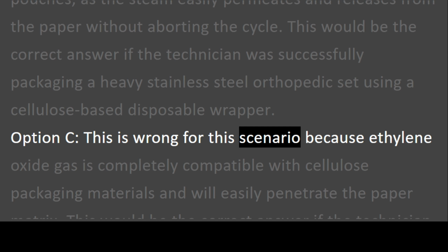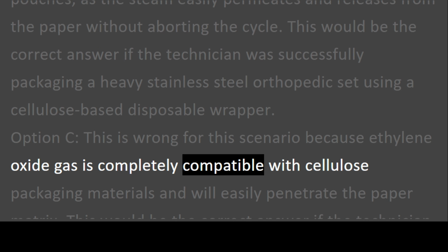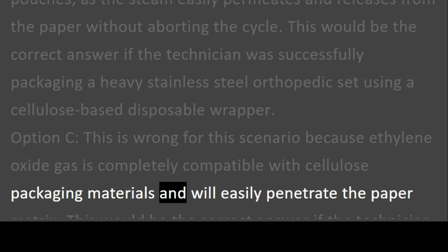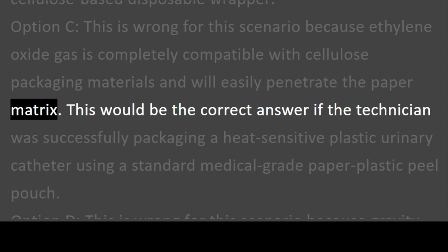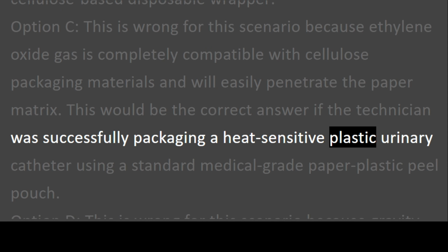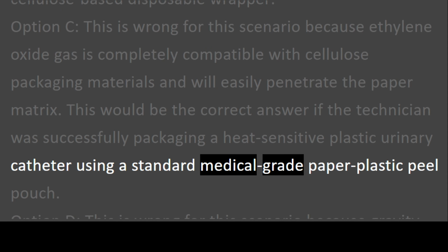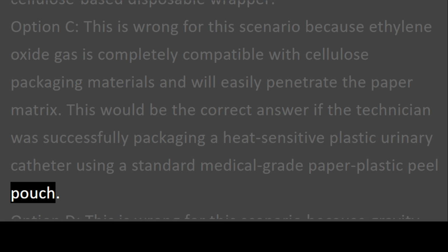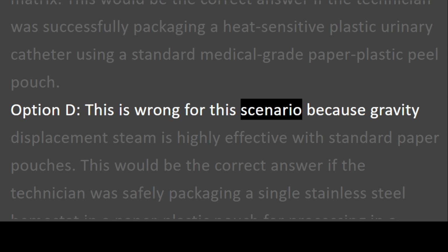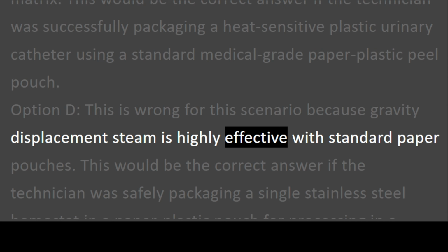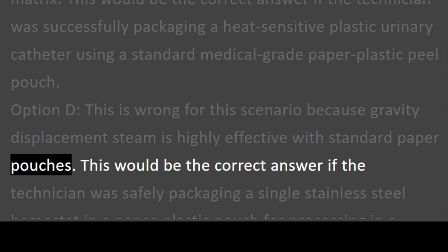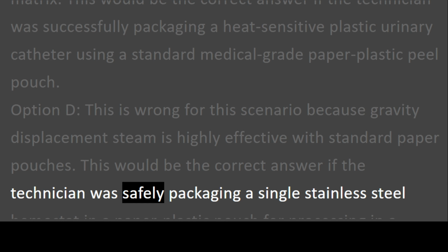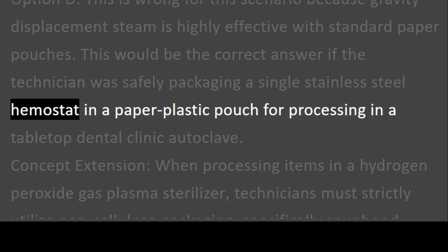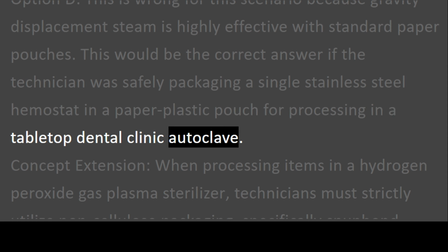This is wrong for this scenario because ethylene oxide gas is completely compatible with cellulose packaging materials and will easily penetrate the paper matrix. This would be the correct answer if the technician was successfully packaging a heat-sensitive plastic urinary catheter using a standard medical-grade paper plastic peel pouch. Option D. This is wrong for this scenario because gravity displacement steam is highly effective with standard paper pouches. This would be the correct answer if the technician was safely packaging a single stainless steel hemostat in a paper plastic pouch for processing in a tabletop dental clinic autoclave.